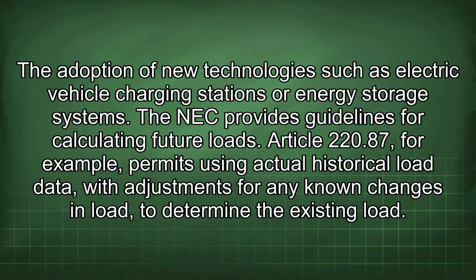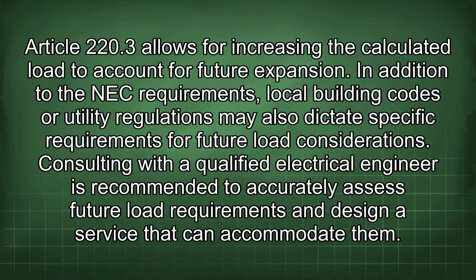The NEC provides guidelines for calculating future loads. Article 220.87, for example, permits using actual historical load data with adjustments for any known changes in the load to determine the existing load. Article 220.3 allows for increasing the calculated load to account for future expansion.